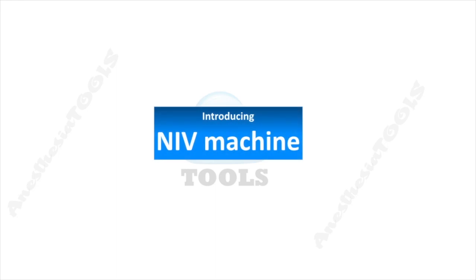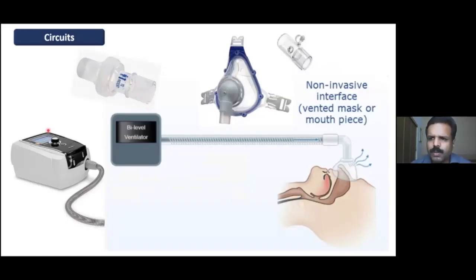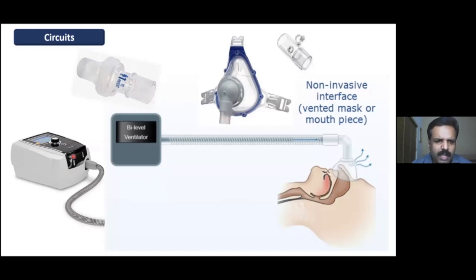Once we have decided in favor of NIV, you need to know your device. It's over to Dr. Anup Kumar to introduce the NIV machine. This is a BIPAP ventilator with a single limb circuit. Usually we have a two-limb circuit, but here only one limb is present, going to the patient for inspiration, and expiratory gas from the patient leaks around the leak port.